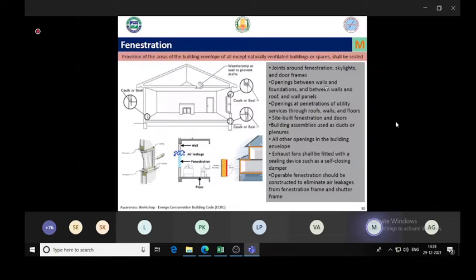Another mandatory requirement is that air-conditioned buildings should be made airtight. Basically, it deals with sealing of the building: the building joints, for example the window sills and window joints, the gaps between foundation and walls, or the gaps when we fix the exhaust fans. All the gaps across the envelope need to be sealed properly and sufficiently. It could be weather sealing or any other method of sealing, but the building should be made airtight. This is a mandatory requirement, and it does not apply to naturally ventilated buildings. The idea is again to minimize unwanted heat, air ingress or air egress.